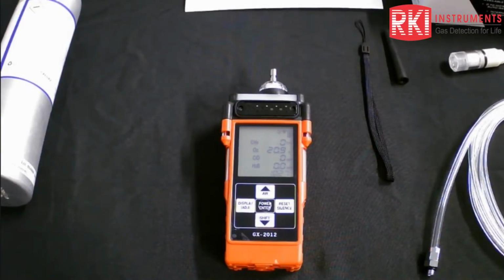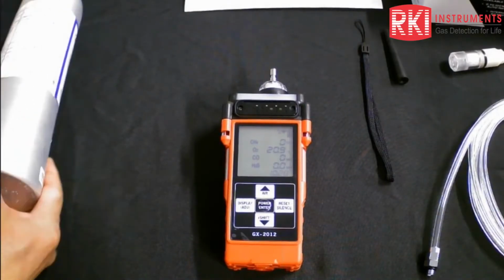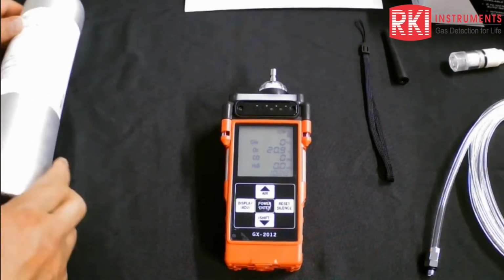Right. So when I work with our transmission pipeline guys, they almost use the two sensors as independent verification that what they believe is happening in the pipeline is happening in the pipeline. Yeah. So we strongly recommend the O2 sensor be present on board with the LEL and catalytic sensors for that verification purpose, as John's talking about.